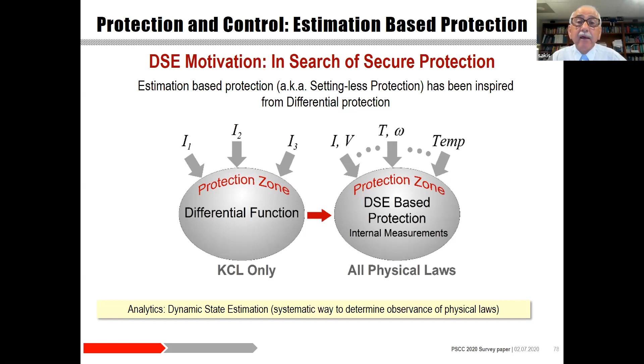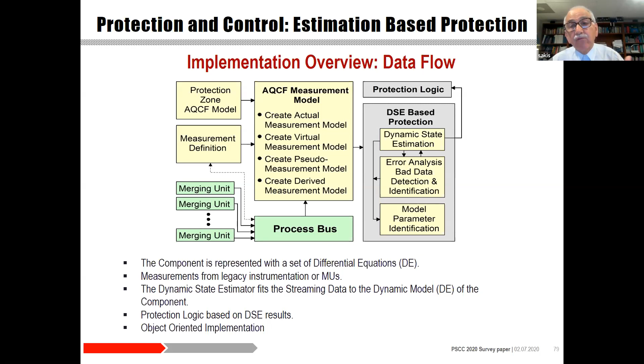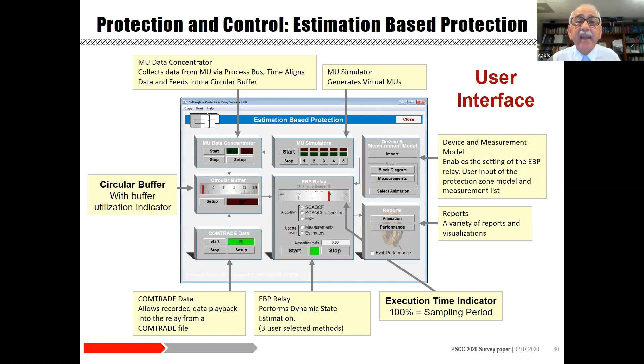Time is running out. The way this relay operates is that we have the merging units shown here, which are data acquisition systems. Of course, we need a mathematical model of the measurements that we've taken. In addition, we can generate virtual, pseudo, and derived measurements based on the topology of the device we have. Then we have a number of measurements, and we run them through the dynamic state estimation, which gives us a plethora of information. Here is the user interface of the relay. A lot more possibilities now. And what I want to focus on is that the dynamic state estimation is computationally intensive.